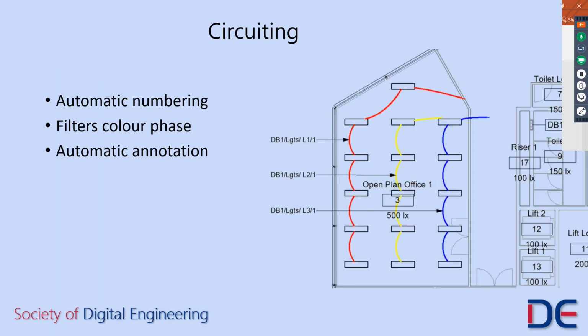Okay, so how are we going to circuit up this lighting array that we've created? And how are we going to do that in a smarter way than just drawing lines between our light fittings? Well, here, what I've done is I've created some circuits. So we've moved from the outside to the inside of the space, and the circuits have been automatically applied by the software. Now, we're using a three-phase distribution board here, and as a bit of a traditionalist, I like to use my old phase colours of red, yellow, and blue, which are now obviously known as L1, L2, and L3.